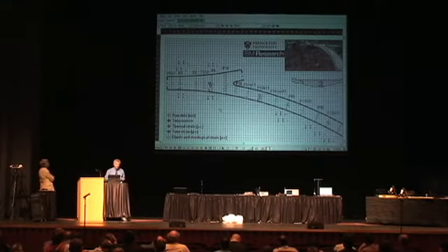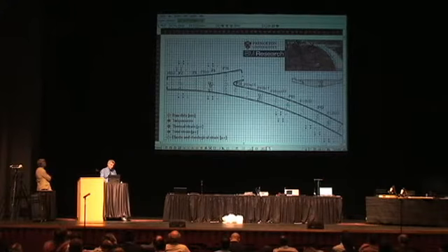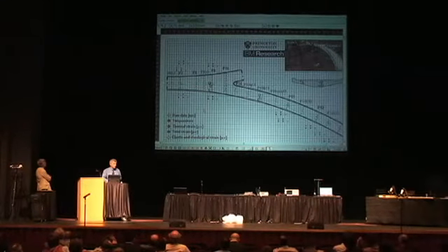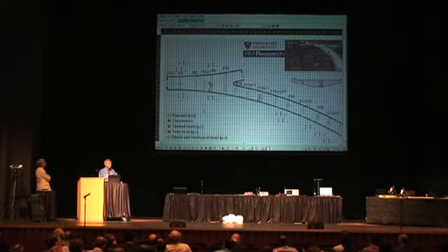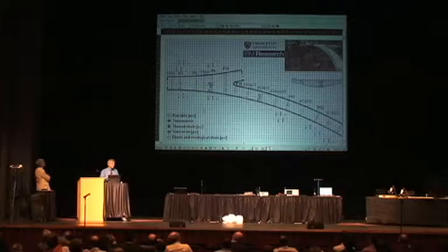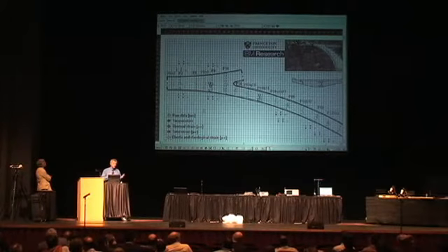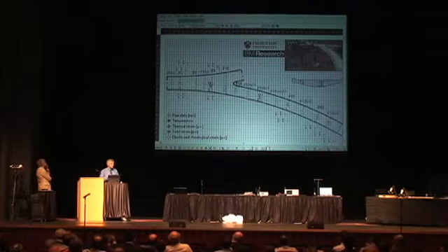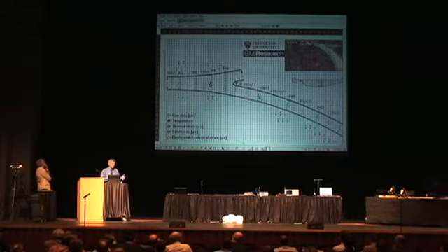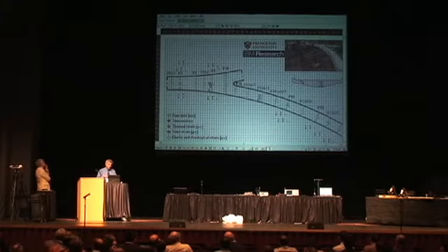You can have much more if you want. And those 5 points are: yellow is raw data, red is temperature, then the blue is total strain calculated, so the data is automatically processed and calculated. And then we have the thermal strain, which is essentially temperature multiplied by thermal expansion coefficient. And then we have elastic and rheological strain, which is in gray color here. And what we see here is the difference between the total strain measured by the sensor and the thermal strain.